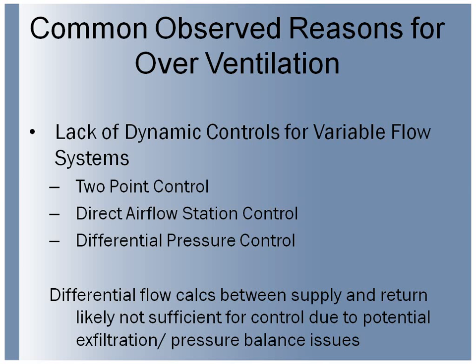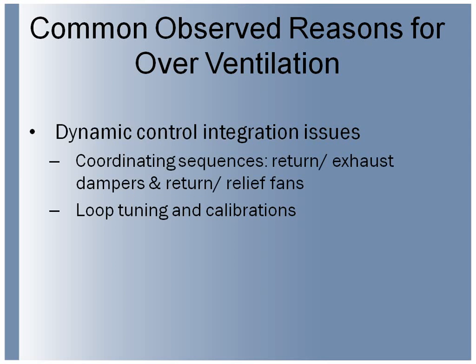Some we see out there with a direct airflow station, so we're using like a Ruskin damper situation and measuring the airflow directly and using that as a feedback signal. Differential pressure control between the mixed air plenum and the outside condition can be a way to do it. We've seen differential flow calcs between supply and return fans. That tends not to be very accurate. Could be calibrated, but is dependent on a lot of other factors in the building, so not necessarily a good way to do dynamic control.